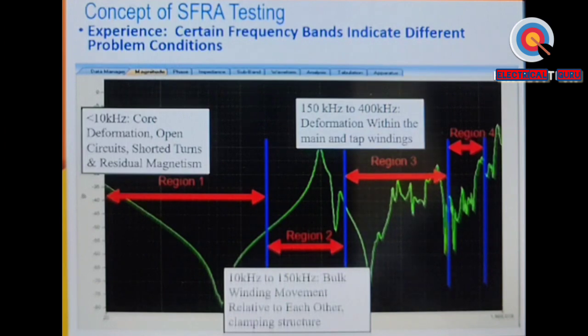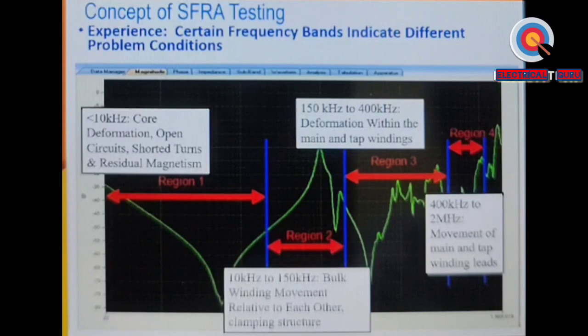And if we see distortion between 400 kilohertz to 2 megahertz, it is more a movement of the main and tap winding leads. So tap winding leads have also suffered some distortion. This will be reflected in this region. So we will be taking the case studies to explain how these regions are, how the problem is seen in the region, and then what exactly was the fault identified in the transformers.